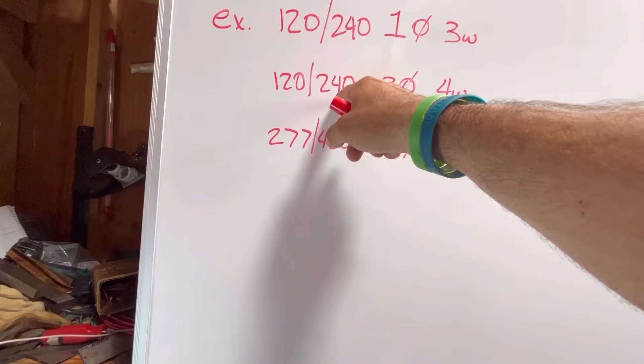Delta divides. And what I mean by that is if these numbers divide evenly into each other, meaning 120 will divide evenly into 240, it's going to be a delta. And if it does not, for example, like 277 and 480, well, those two numbers do not divide evenly into each other. So these would be a Y. So again, delta divide. 120 divides evenly into 240. If it does, it's a delta.